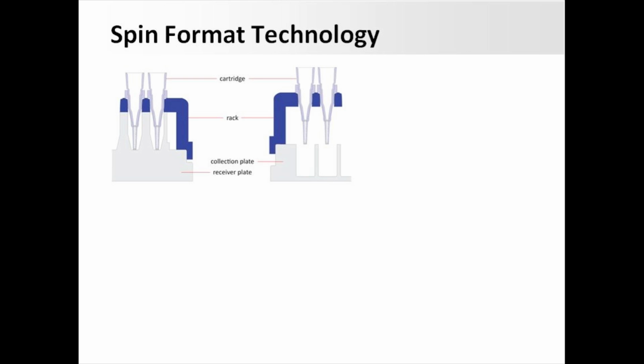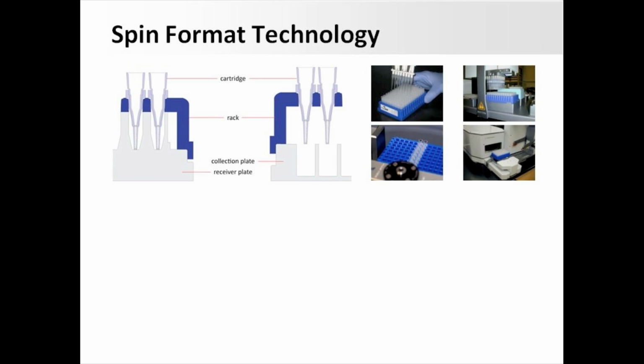In addition to that, we've engineered a special piece of labware called a receiver plate, where the wells actually go up inside the rack, and the top of the packed bed is below the top of the receiver plate well. And the bottom of the cartridge, the outlet of the cartridge, is suspended just above the bottom of the receiver plate well. And in a second I'll show you what that's for. But this technology can be used with manual liquid handling. As you can see here, you can load in any number of samples at a time.